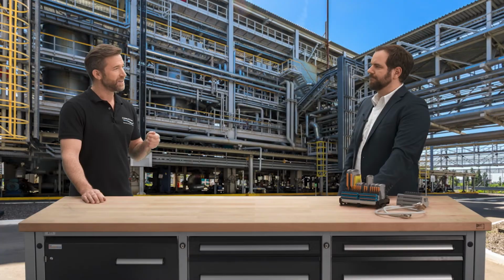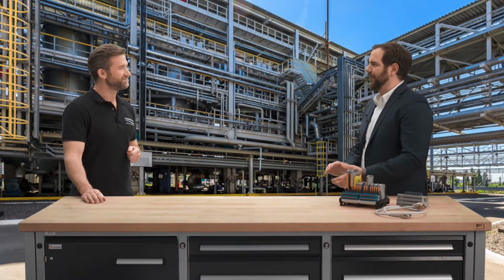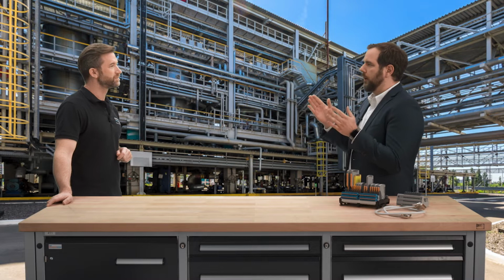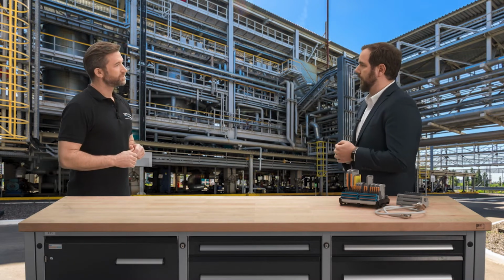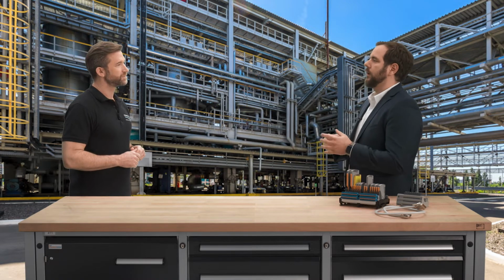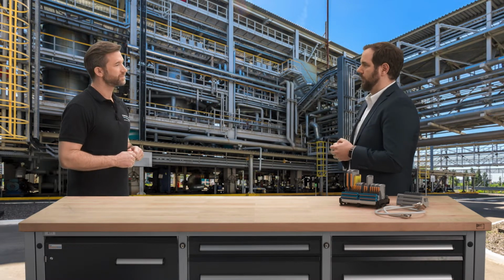A new plant concept with decentralized unit packages and universal I/Os has become a game changer. Can you give us an insight? Sure, Sascha. Compared to standard I/O systems, universal I/O systems offer the possibility that they can process any signal that you would expect in a process plant. In classical structures, you would have big marshalling cabinets where the signals are sorted by its type. This is no longer necessary with universal I/O systems.